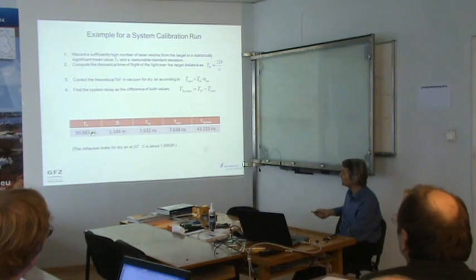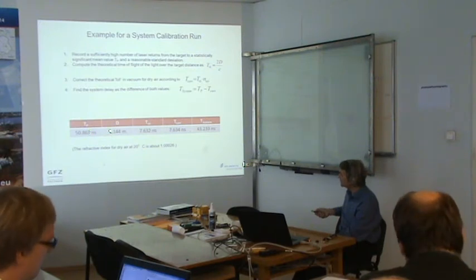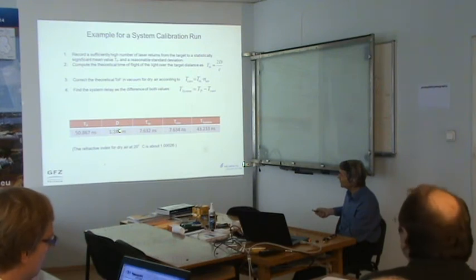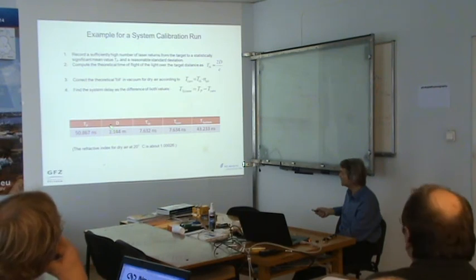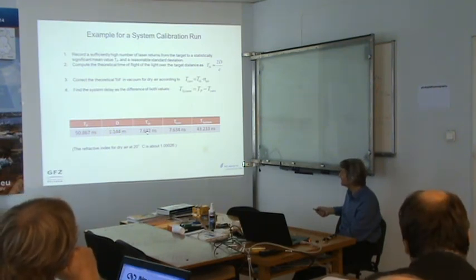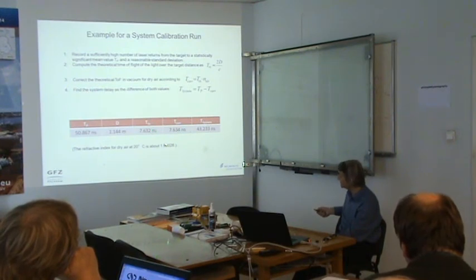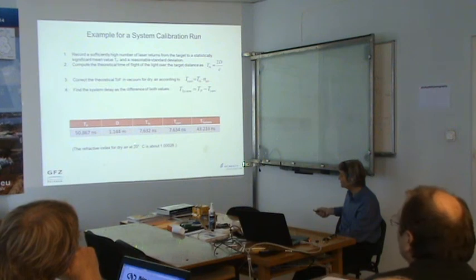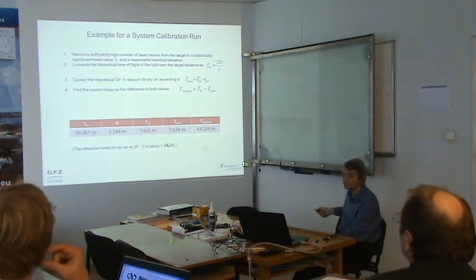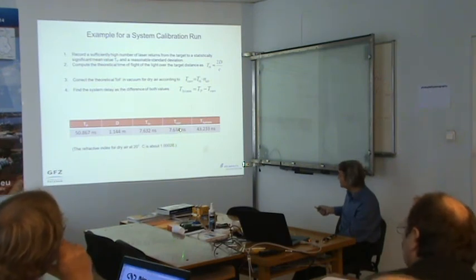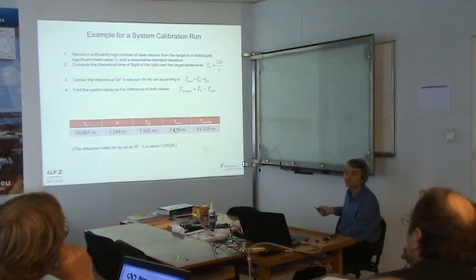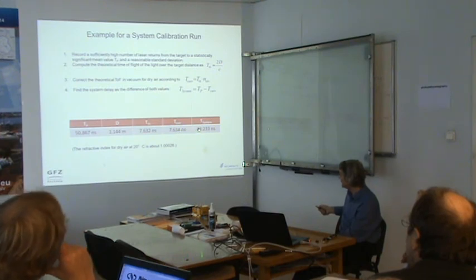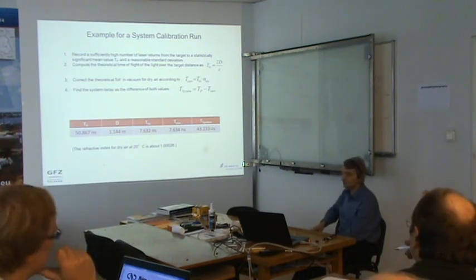This is a real calibration we have performed in Potsdam with this TPL system. The mean is 50.867 nanoseconds. The small prism is attached at a distance of 1.144 meters with respect to the invariant point. We'll get back to the determination of the invariant point later. That gives rise to a theoretical two-way traveling time of 7.632 nanoseconds. If we correct it, going into the table for dry air at 20 degrees Celsius, 1.00026, you see this is not deviating too much from 1. We enhance this by 2 picoseconds. 2 picoseconds is practically nothing. This is less than a millimeter of flight distance. And we get the system delay as 43.233 nanoseconds. We keep that in mind, but we will see it on a later slide again.